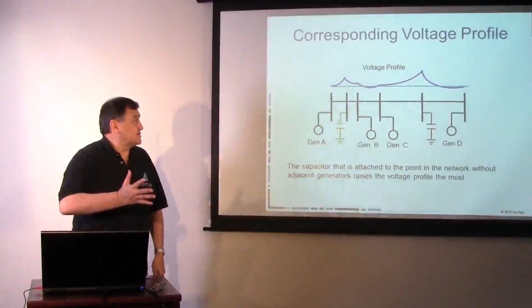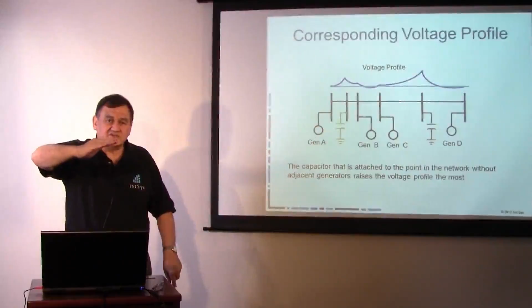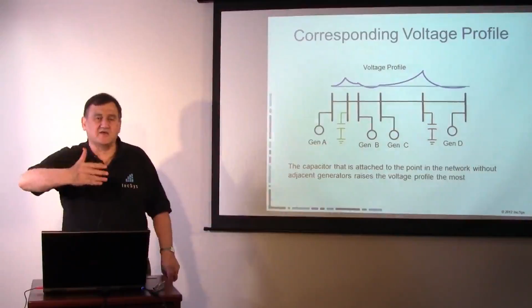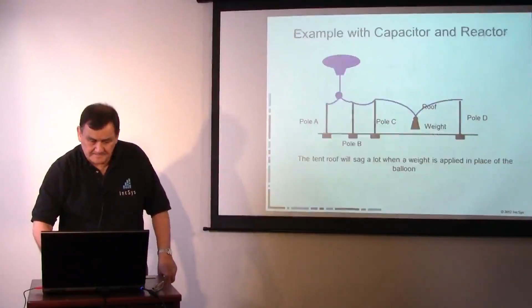It can actually be beneficial to apply capacitors close to your generators. You may not raise the voltage much, but you'll take that generator, which may have been producing megavars, and by adding the capacitor, you will move that generation down to the point where it may be more neutral. It's neither consuming nor producing. That means by adding the capacitor ahead of time, that generator has more room to produce megavars when you have a line outage. So it's important to use your capacitors strategically, and think ahead, not just look at the voltages right now. Think ahead about what's going to happen as you have major contingencies on your system.